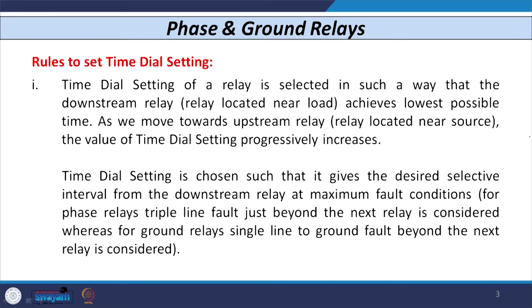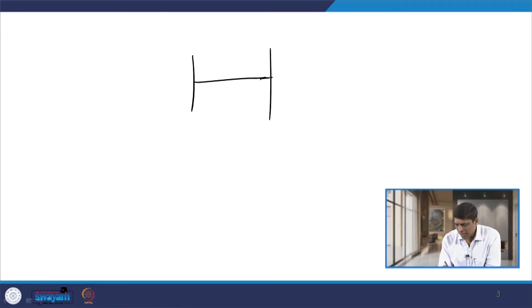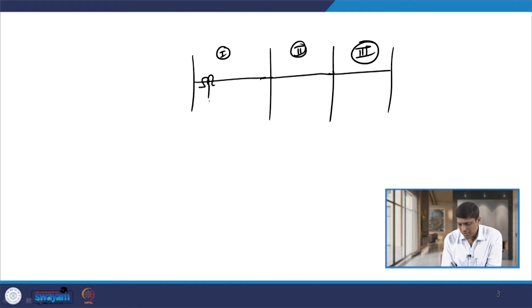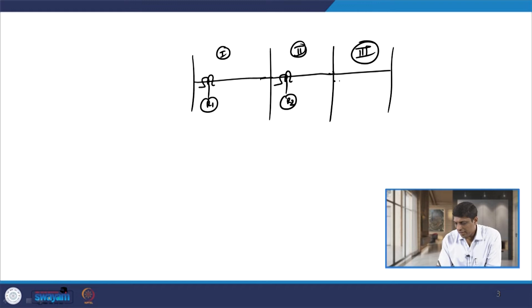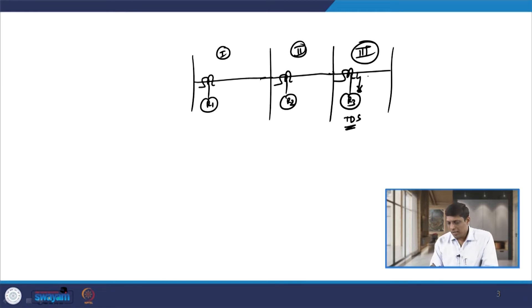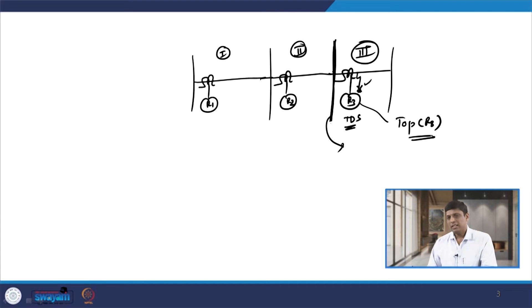For phase relays it is the triple line fault, and for ground relay it is the line-to-ground fault. Let us say we have a multi-section radial feeder network with section 1, section 2, and section 3, and relays R1, R2, and R3 connected in sections 1, 2, and 3 respectively. When we decide the time dial setting of relay R3, we consider the fault condition immediately after the relaying point, and normally we take the fault MVA at that bus.